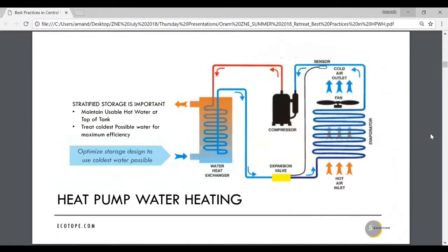So big picture heat pump water heating - we all know what heat pumps are, I'm going to assume we all know what heat pumps are. They move heat, we've got a refrigeration cycle between two sources, an outdoor source and in this case a water source. The point of this slide is showing that stratified storage is hugely important. It's important for the function of the heat pump, and it's also important for just delivery of hot water.